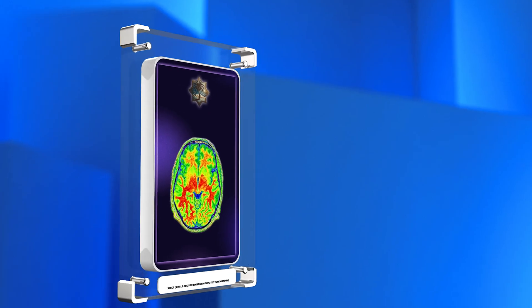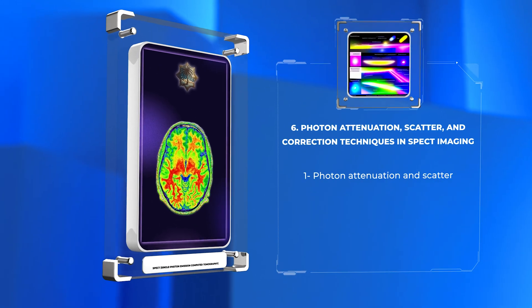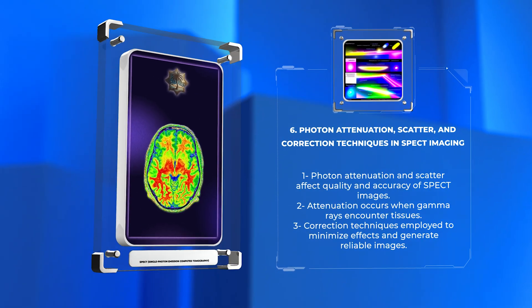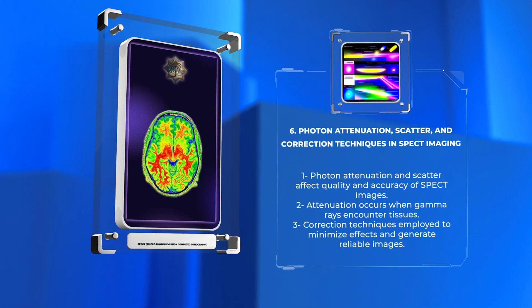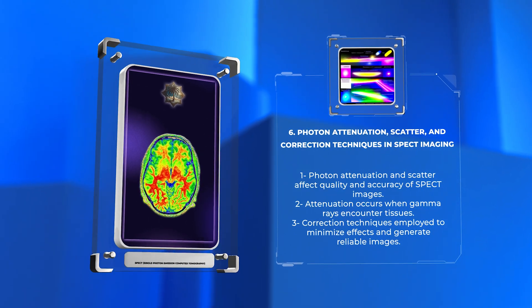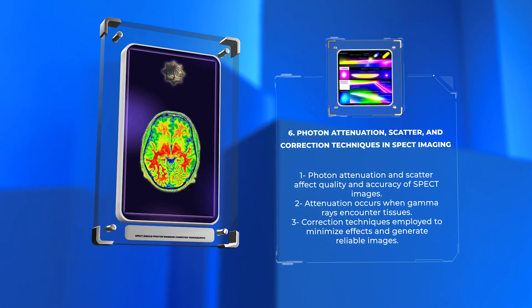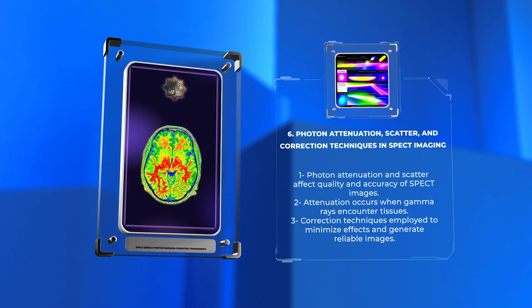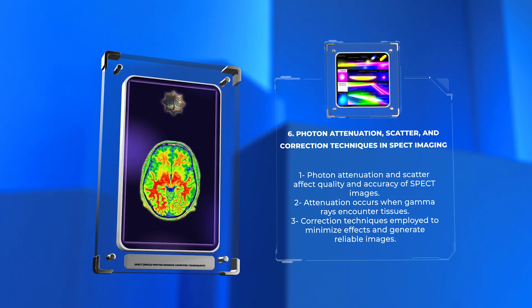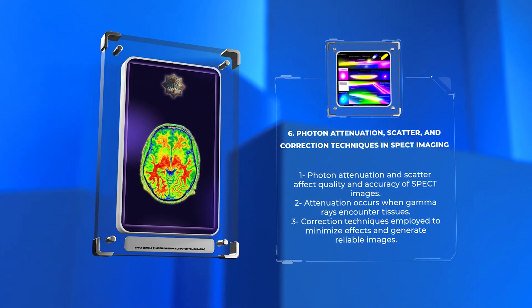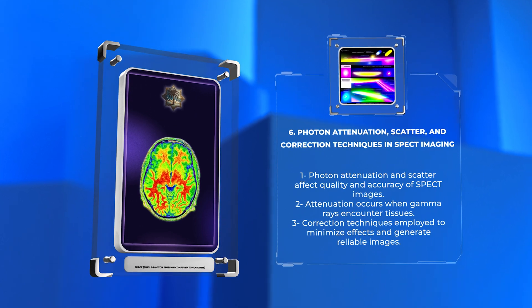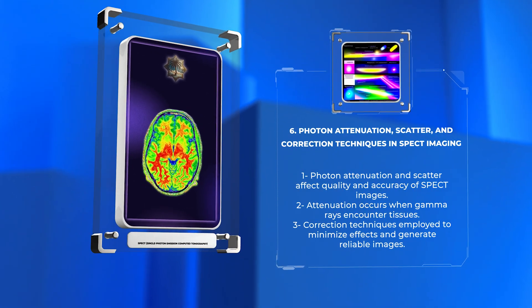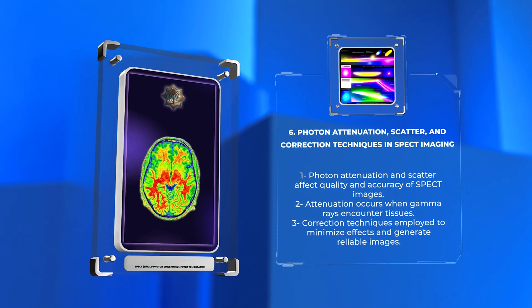Photon attenuation and scatter are physical phenomena that can affect the quality and accuracy of SPECT images. Attenuation occurs when gamma rays encounter various tissues, leading to their absorption or scattering. Correction techniques, such as attenuation correction methods and scatter correction algorithms, are employed to minimize these effects and generate reliable images, aiding in accurate diagnosis and disease management.